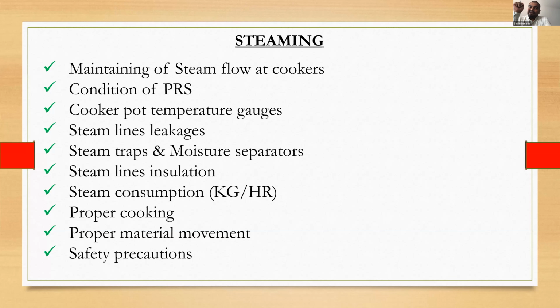What will happen if in the steam line you have 8 bar pressure? It will reduce it to 4 bar and it will continuously give that. Even if it is 4 bar there, it will give 4 bar only. Even if it is 8 bar, it will give 4 bar only. We have to adjust that.